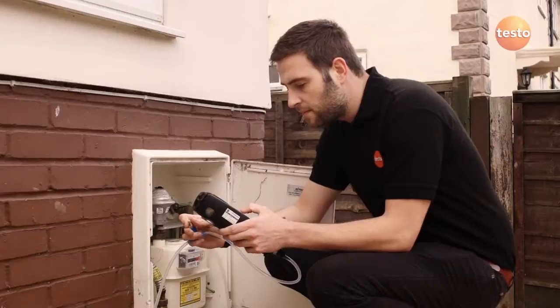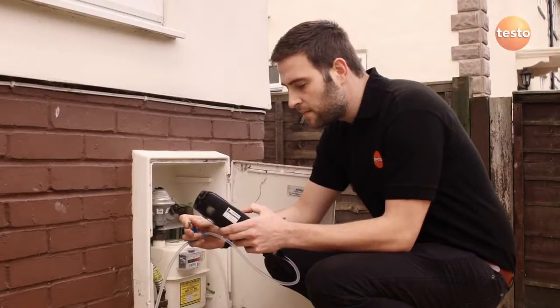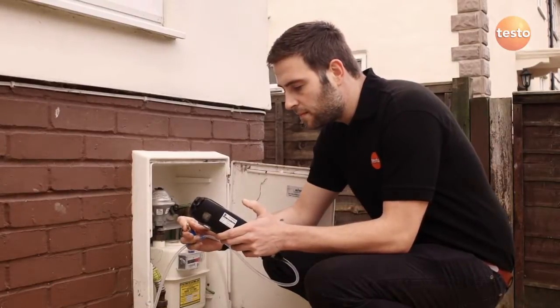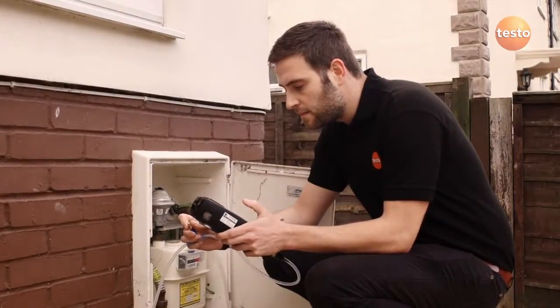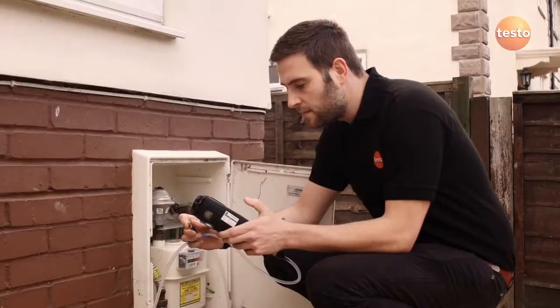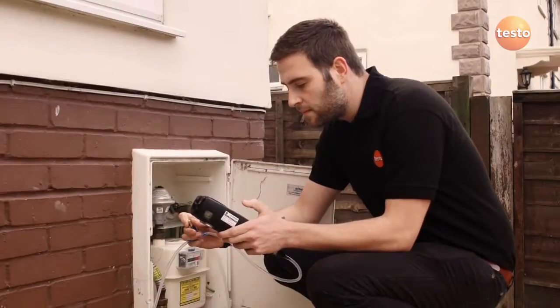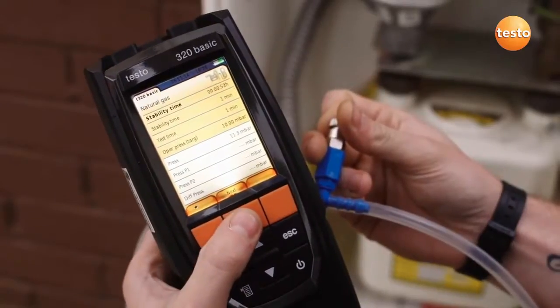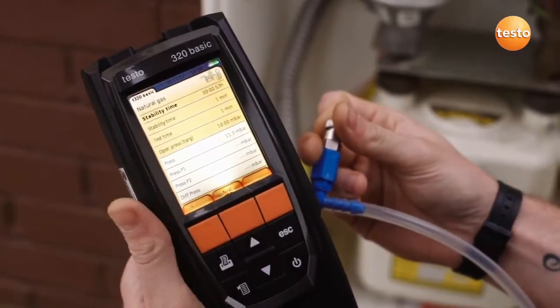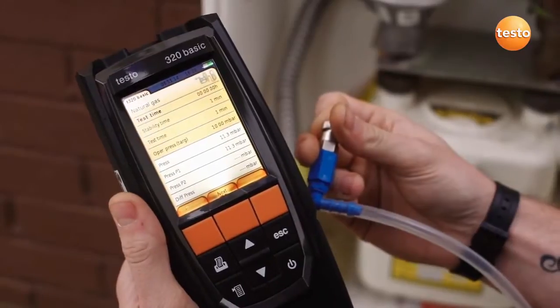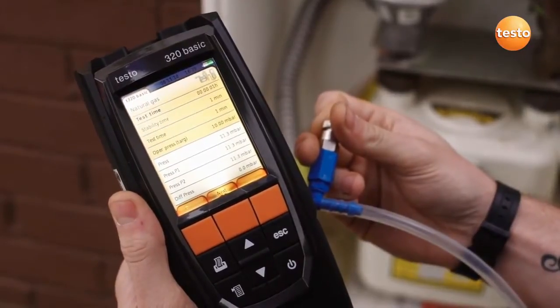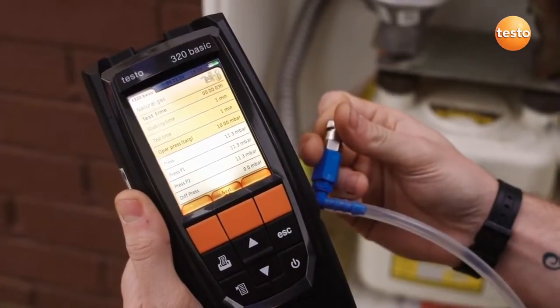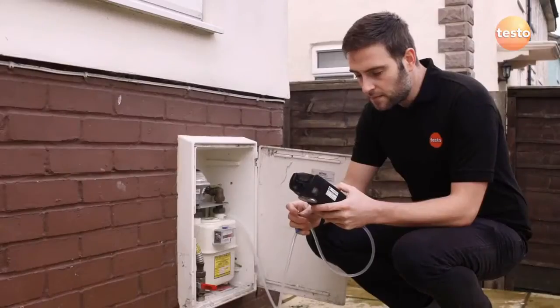With the pressure set to 10 millibars, start the stabilization time. If the pressure varies during this period, then reset and start again. At the end of the stability test, the analyzer immediately goes into the timed let-by test where it measures and logs pressure for the preset test time.